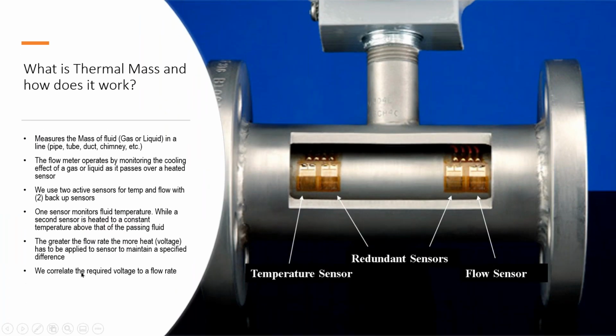Jumping into the presentation, let's talk about how thermal mass works. For one thing, Thermal Instrument only does thermal mass technology. We don't offer any other types of measurement technology. Thermal mass measures the mass of a fluid in a line, and that fluid can be a gas or a liquid. That's one differentiator Thermal Instrument can provide: we can measure both, because we have calibration stands that are set up for both liquids and gases.